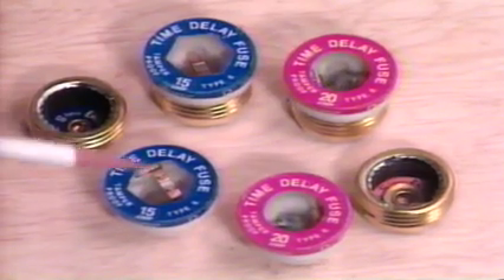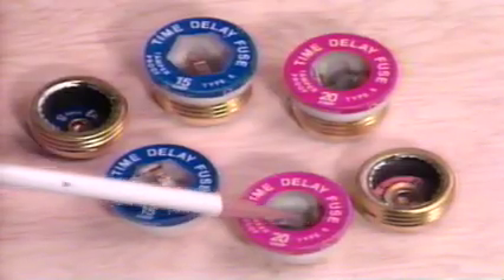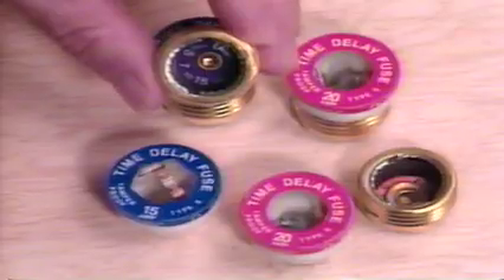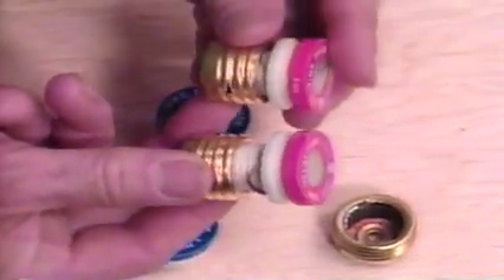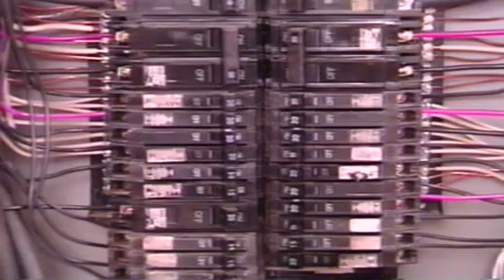Today there are fuses designed to prevent you from using a fuse rated higher than what the circuit is rated for. These fuses, called S-type fuses, use an adapter that won't allow you to install the wrong size fuse. So you can't install a 20 amp fuse in a 15 amp fitting. Most distribution panels installed after 1965 use circuit breakers to protect the individual branch circuits. The circuit breaker has a permanent metal strip that bends as current flows through it, from the heat of the current. If too much current flows through the metal strip, the circuit becomes overloaded. The strip then bends enough to open the switch and stop the flow of electricity. This is called a tripped circuit breaker. Circuit breakers trip for the same reasons that fuses melt. Too much current caused by an overload, or there is a short somewhere in the circuit.